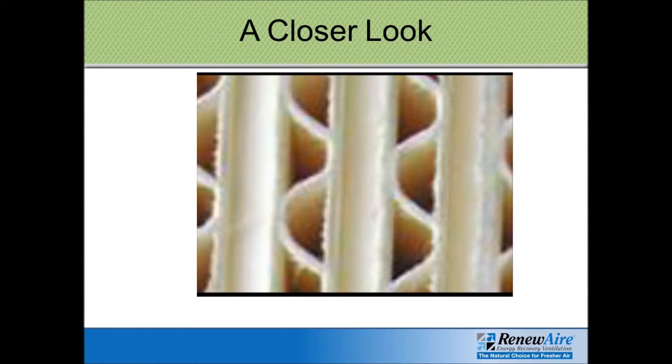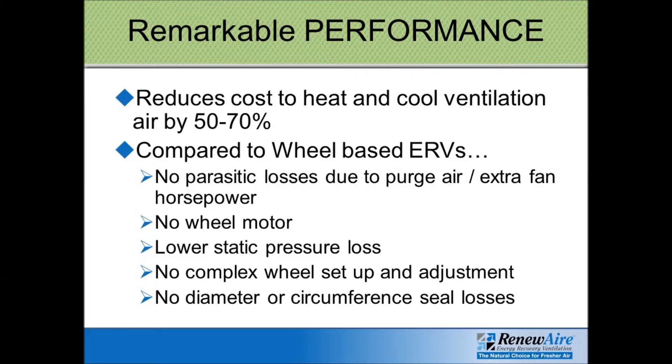Here's a close-up image of the core — you can see the air passages going in one direction, and then every other row has the air coming in from a 90-degree angle. Using the RenewAire unit can save anywhere from 50 to 70% on the energy bill to heat and cool your outdoor air. So it pays for itself really quickly, and it's a very efficient unit. Also, there's no need for a third motor to spin the wheel like with a desiccant wheel type unit. Typically, the pressure drop through the core is less than the pressure drop through a desiccant wheel.